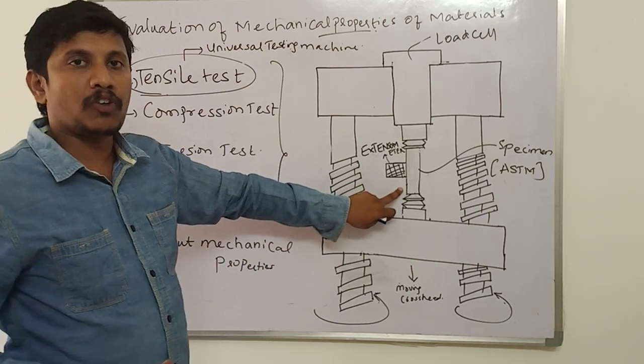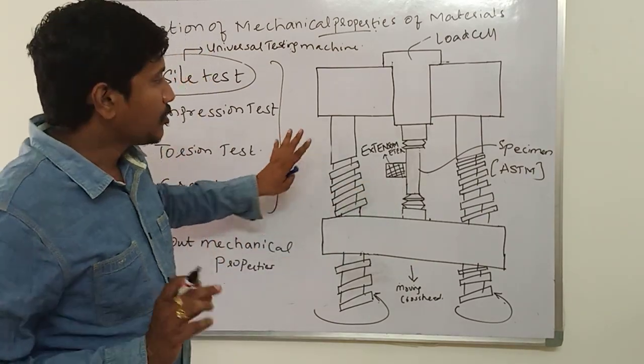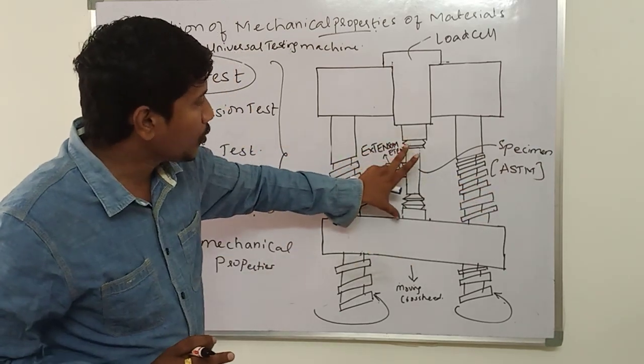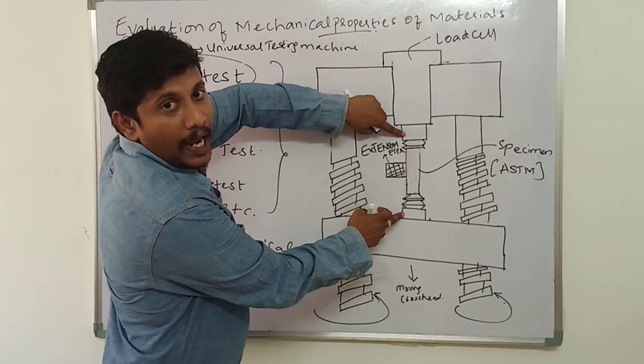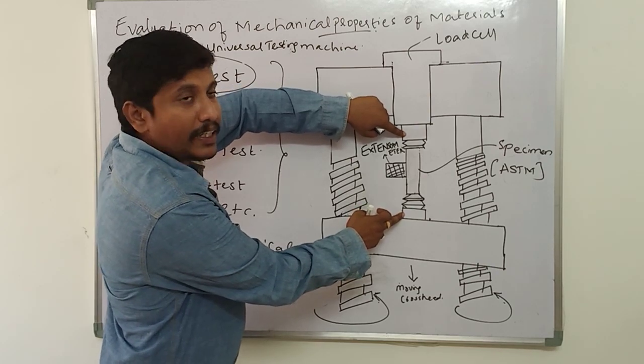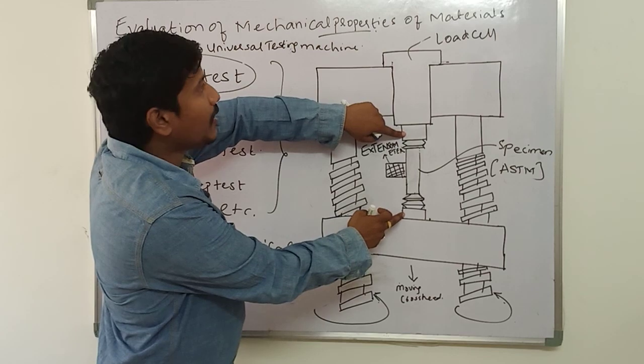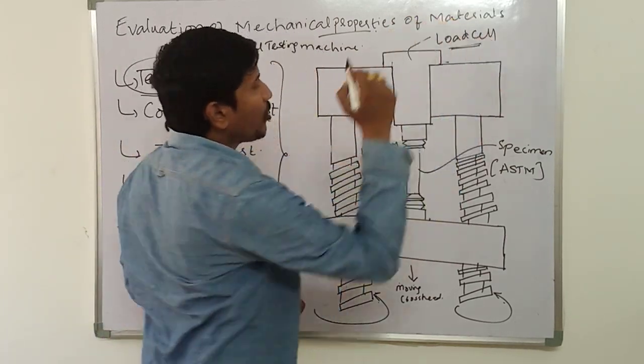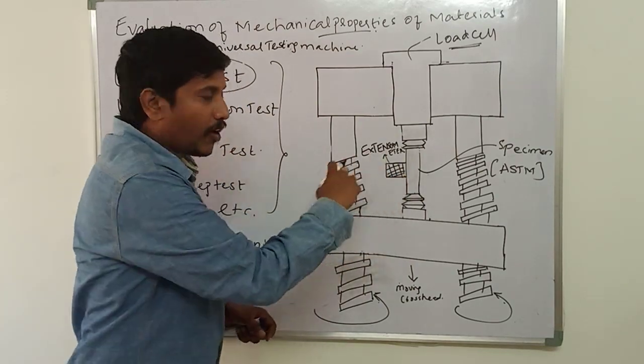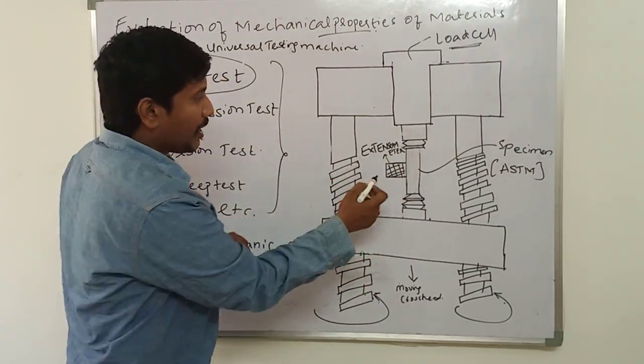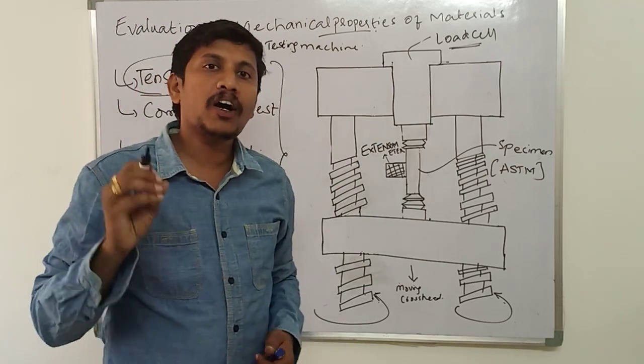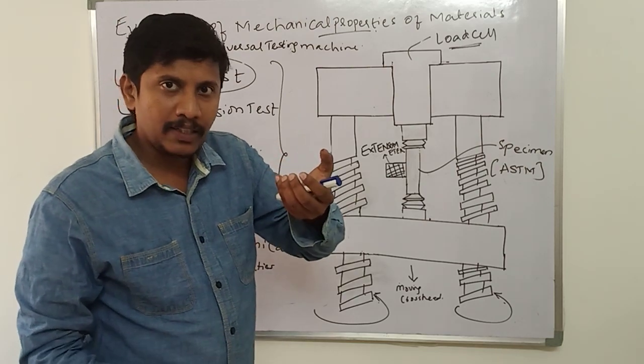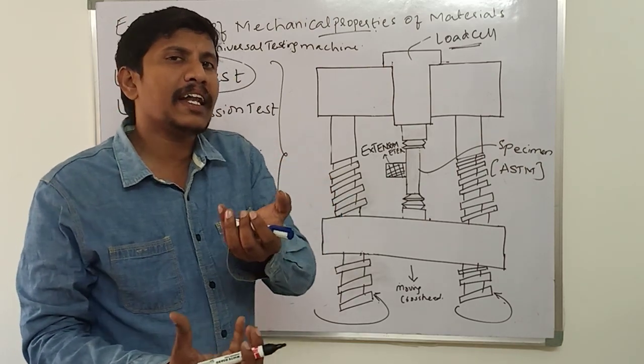Thus we will be finding out the properties with this tensile testing machine. A standard specimen as per the ASTM standards is gripped between the two heads and a progressively increasing load is applied. The load is measured with the help of a load cell, and the extension of the specimen is measured with the help of an extensometer or strain gauge.